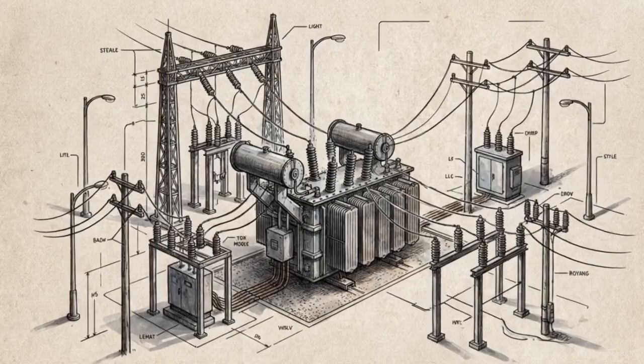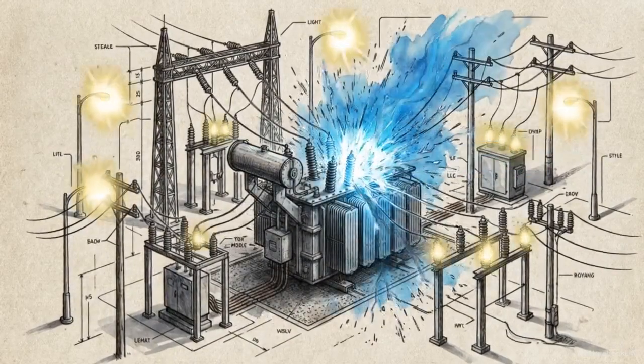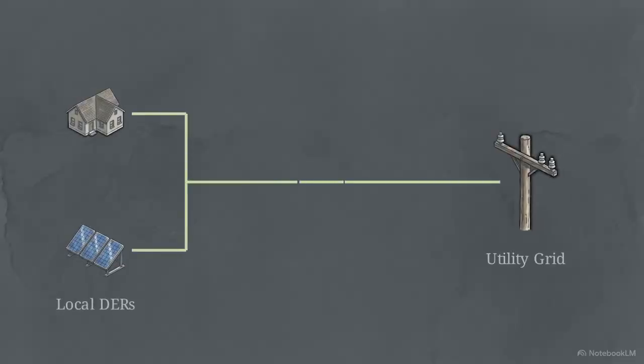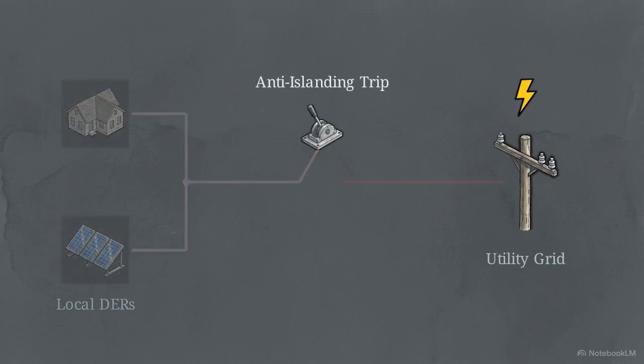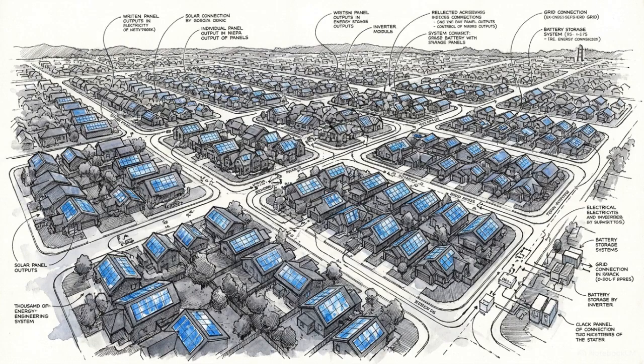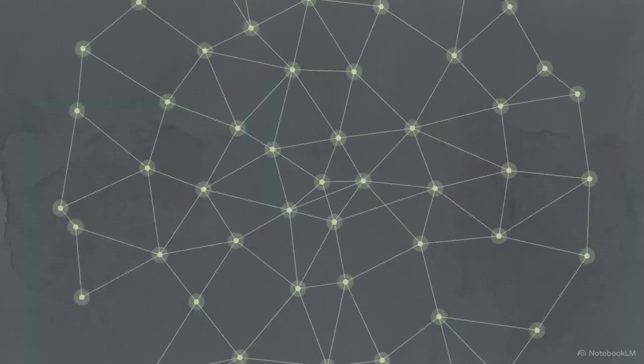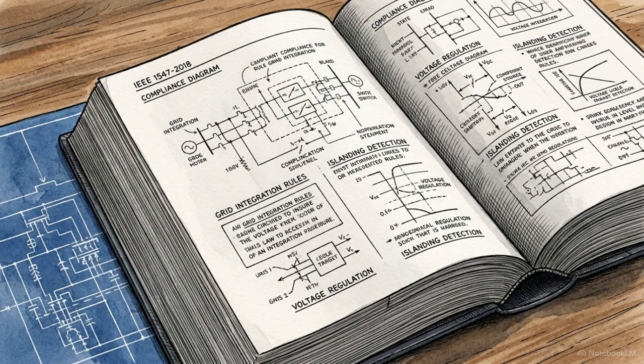At the exact millisecond a major fault occurs, a massive voltage sag propagates rapidly down the distribution feeder. Historically, safety regulations required anti-islanding. Any local solar array had to instantly trip offline to protect workers from unexpected currents. But as local generation scales, that logic creates a risk. If every solar inverter trips simultaneously during a voltage dip, the sudden loss of power can cause the entire macrogrid to collapse. The IEEE 1547-2018 standard changed the requirements.